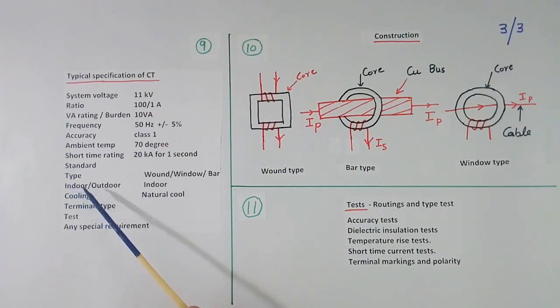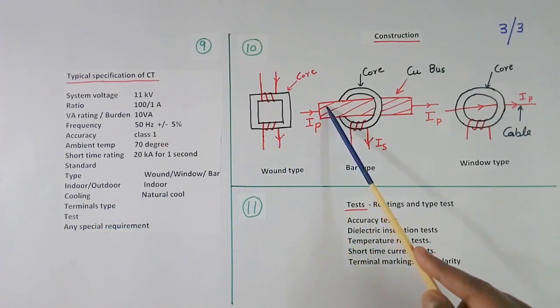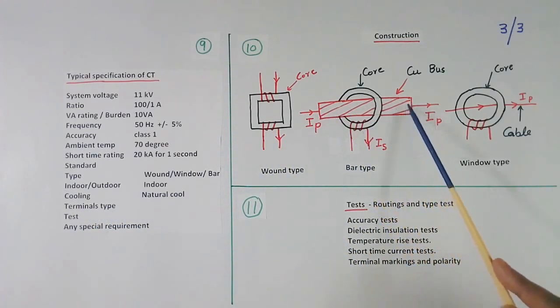Then we have to tell indoor or outdoor. Generally this CT will be outdoor. This is indoor. Suppose you write outdoor, then CT should be made waterproof and sunlight proof. Then terminal type. What type connection we want here. What size of hole will be here. Then test. What are the test we have to do or any other special requirement. We have to write.